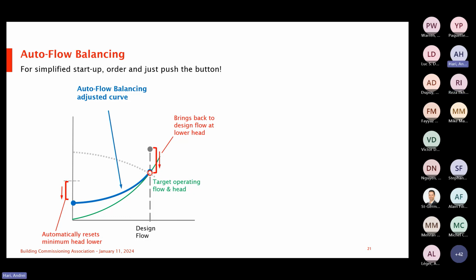What's happening in your system is, as you start closing valves, you're decreasing the demand for flow. So as we decrease the demand for flow, we know that we don't have to run at a higher speed, so we start dropping the speed of the pump. As we drop the speed of the pump, the head is going to drop to the point where it meets the resistance in the system. So if all the valves are closed and your resistance is still 20 feet, it's going to drop to where it's 20 feet and it's going to be moving that much water there.